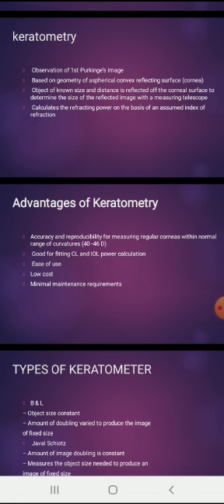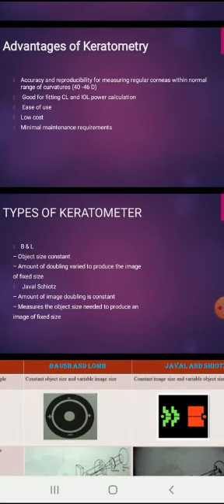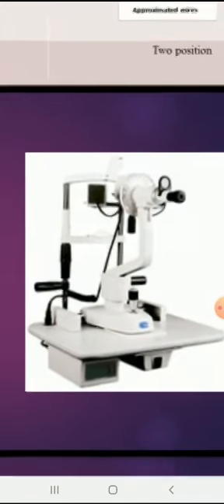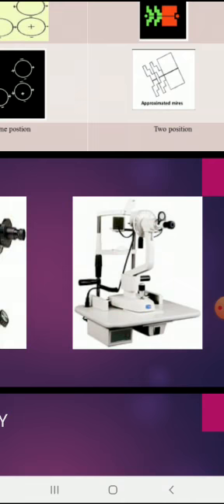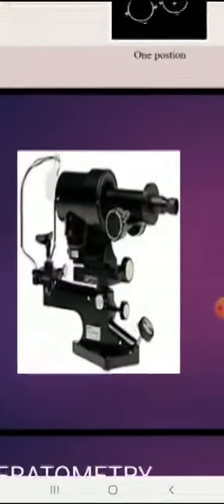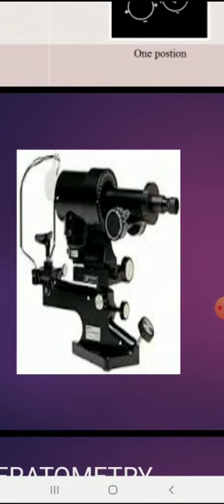Regarding the types of keratometer: either we can make the object size constant or the image size constant. In the Bausch and Lomb keratometer, the object is constant, and in the Javal-Schiotz keratometer, the image is constant. The Javal-Schiotz keratometer was the first invented, but it is not commonly used nowadays. The Bausch and Lomb keratometer is the one commonly used in all clinics.